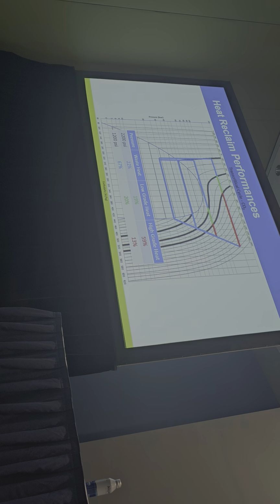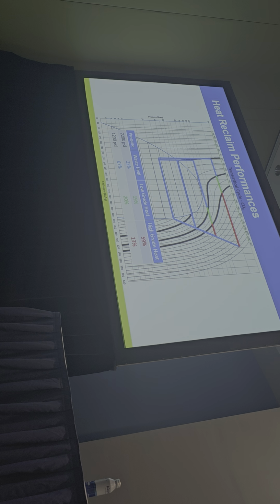Normally, when we do refrigeration, we're trying to have the compressor as close as possible to the highest suction temperature and the lowest condensing temperature, and then we have the highest COP. On CO2, we're running transcritical. Sometimes I push the pressure just a little bit more, and I'm getting a better COP. Why is that?